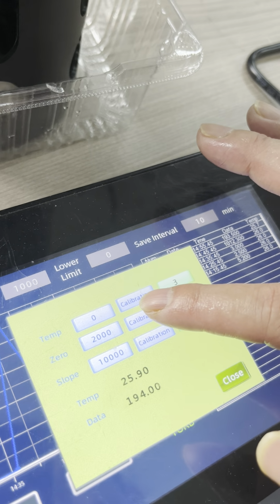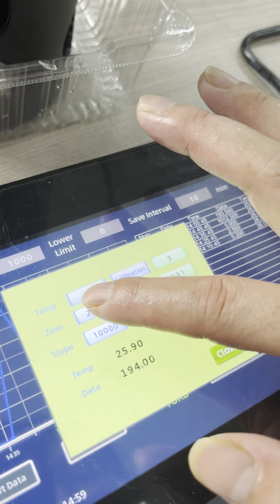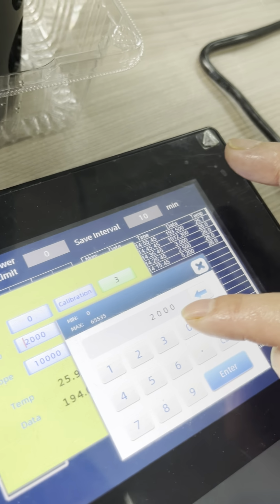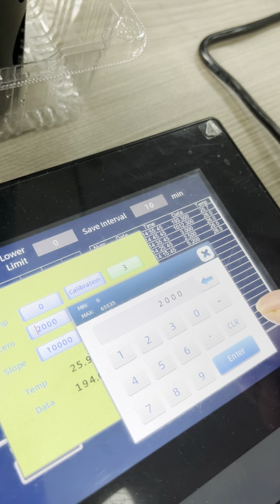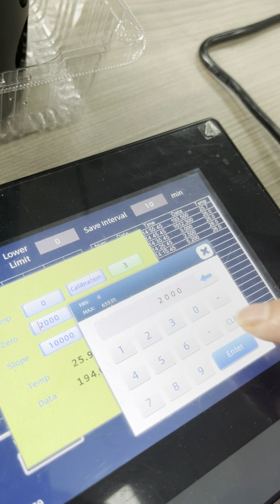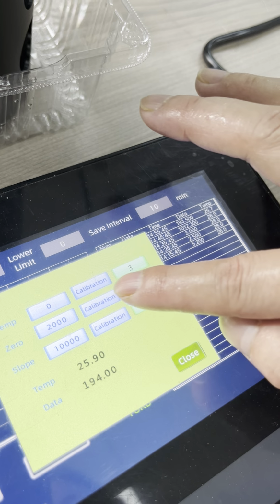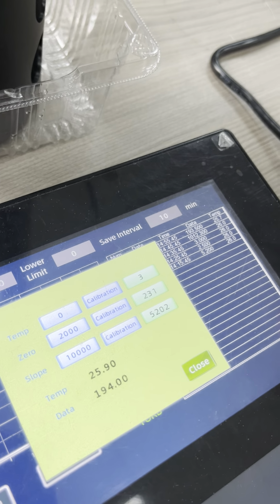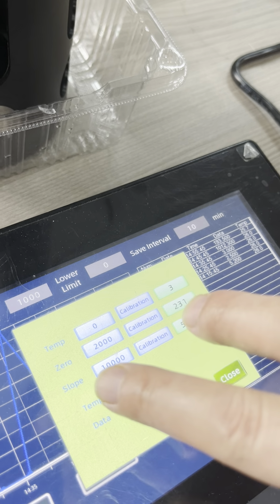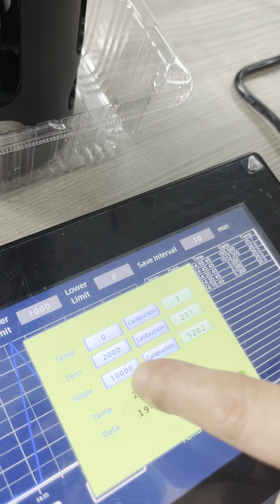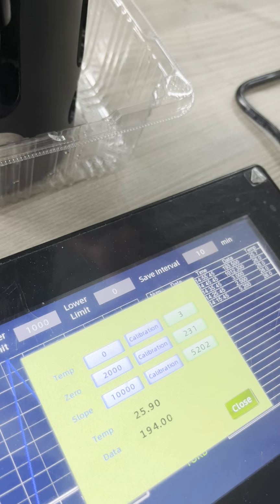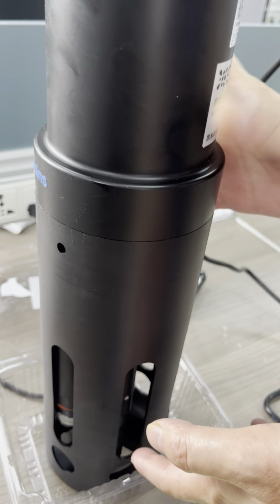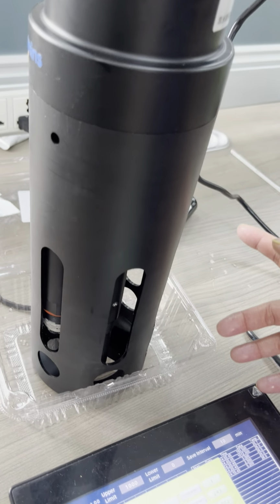Then you click here. You input 200 times 10. That is 2000. Then click enter. Then click calibration. The calibration of zero is done. Now we will do the slope calibration. We put the sensor into standard solution of 1000 NTU.